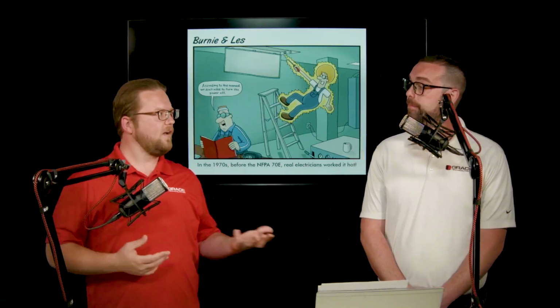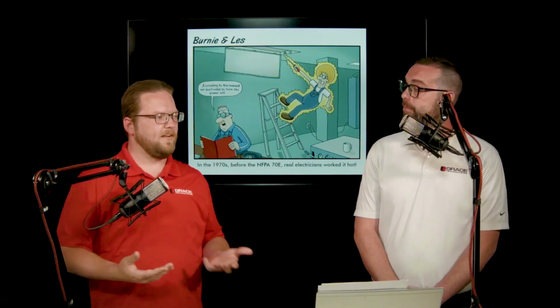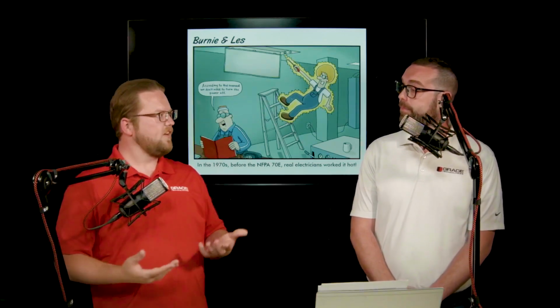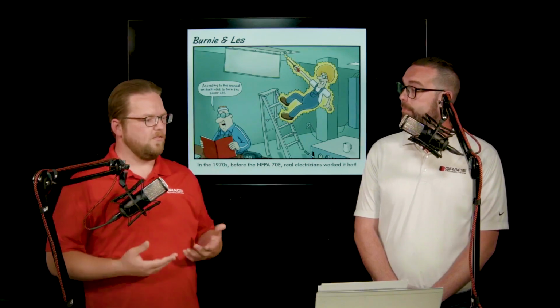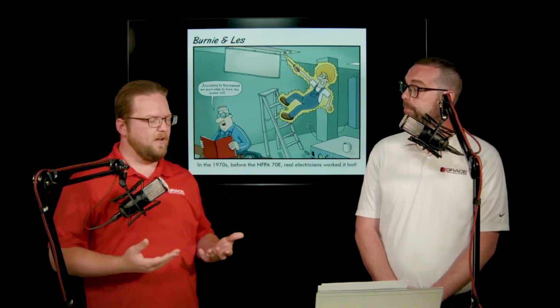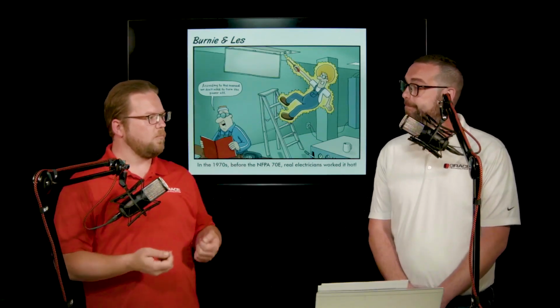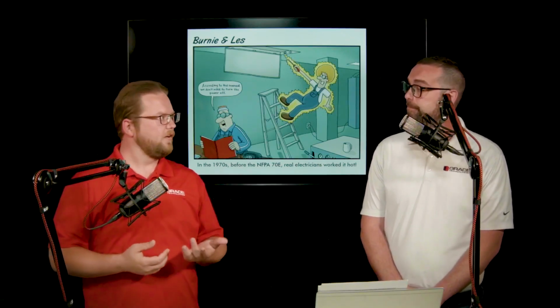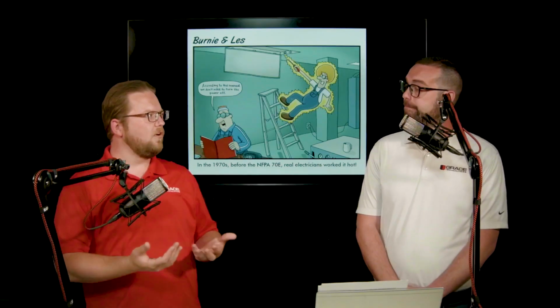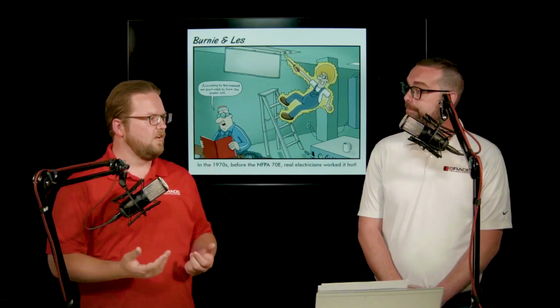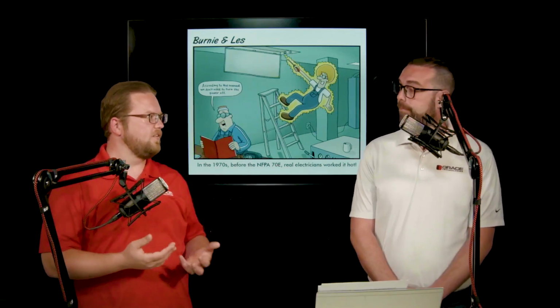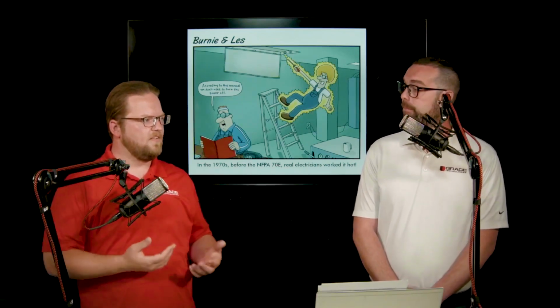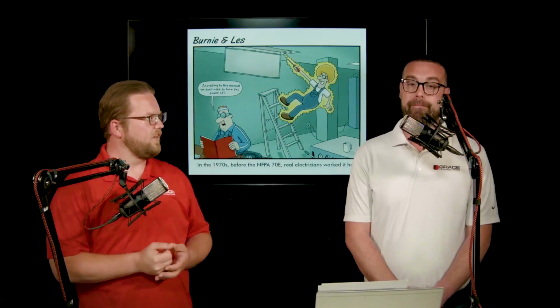So can you give an example of an existing lockout tagout procedure where if we involve the check volt, what that looks like? Because from my conversations, it's been beneficial to where you can still use your portable test meter as outlined in your existing procedures. So there's minimal input that you have to change to your existing procedures. Just a little bit of update on the testing, the qualification, and the documentation side.